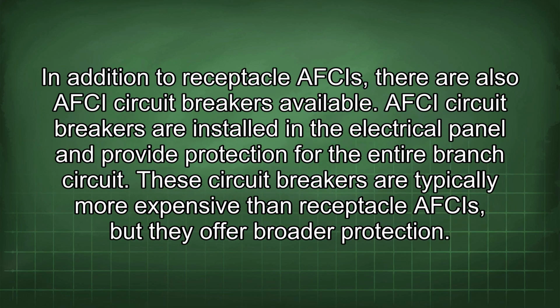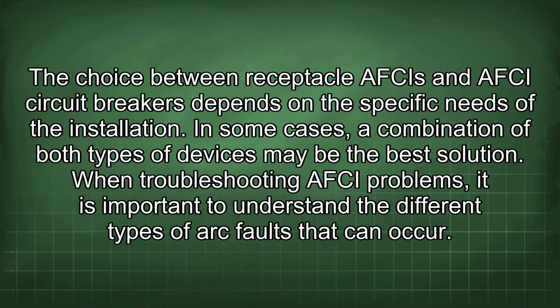In addition to receptacle AFCIs, there are also AFCI circuit breakers available. AFCI circuit breakers are installed in the electrical panel and provide protection for the entire branch circuit. These circuit breakers are typically more expensive than receptacle AFCIs, but they offer broader protection. The choice between receptacle AFCIs and AFCI circuit breakers depends on the specific needs of the installation. In some cases, a combination of both types of devices may be the best solution.